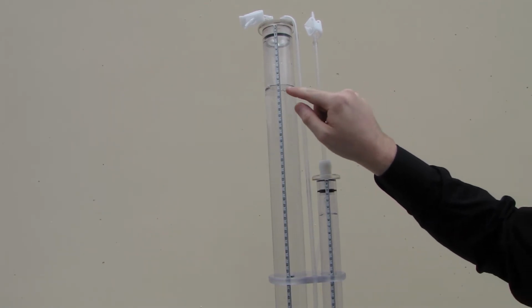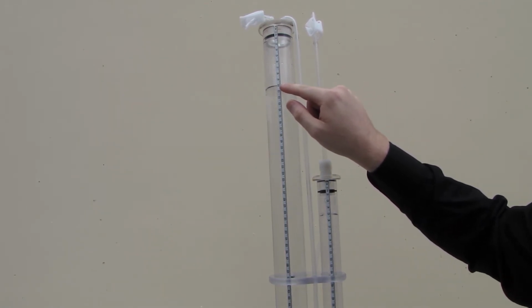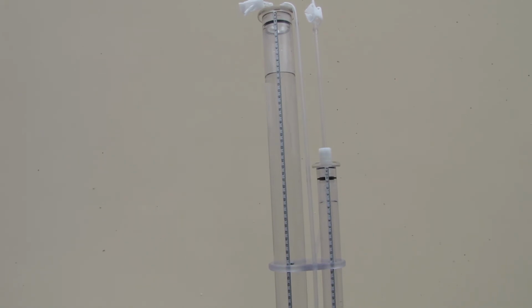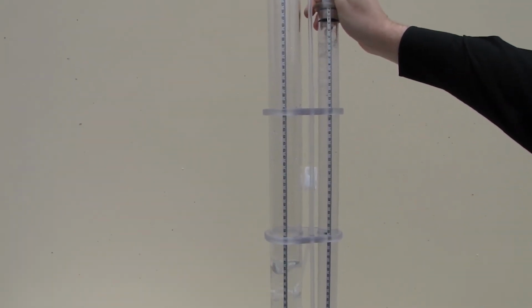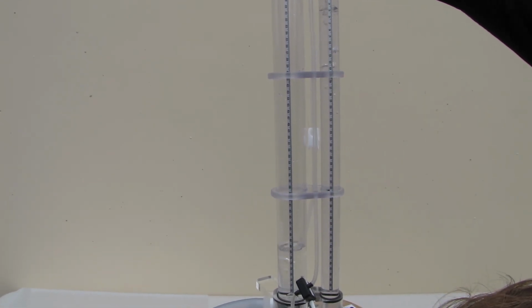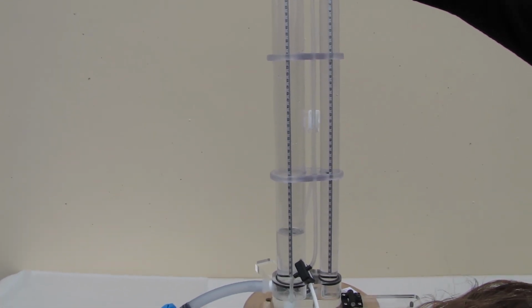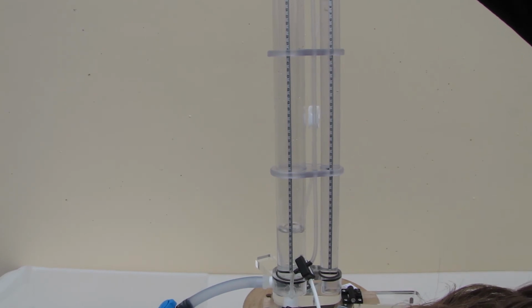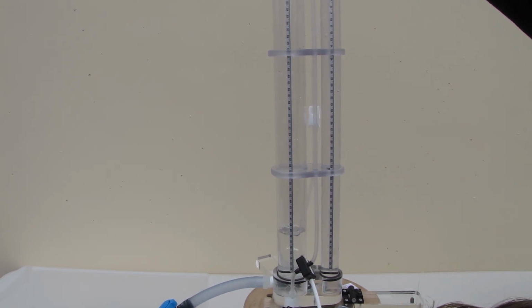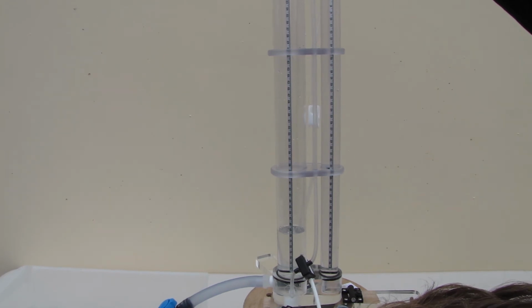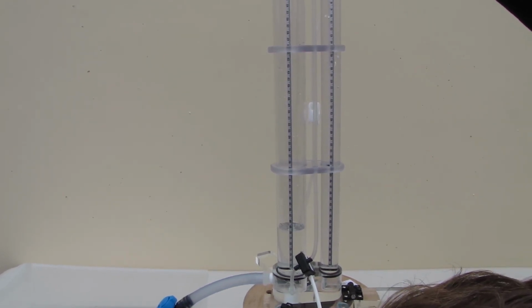If you are calibrating the AIM1, it should be in live mode. Calibration is the process of reading the manual gauge in millimeters and then the millivolts displayed for that particular point on the tower. Shown here is a typical second last calibration point of approximately 700mm. Then at the very bottom of the gauge, the 765mm mark can be used on the lookup table. Beyond this mark on the AIM1, the results will not hold, and this is the maximum level or limit the AIM1 can record to.